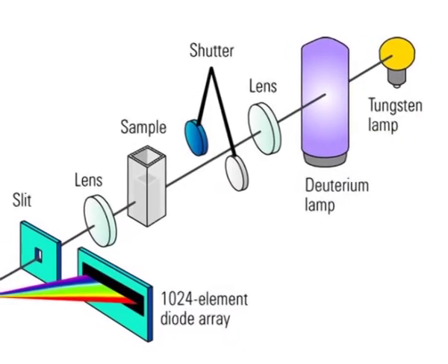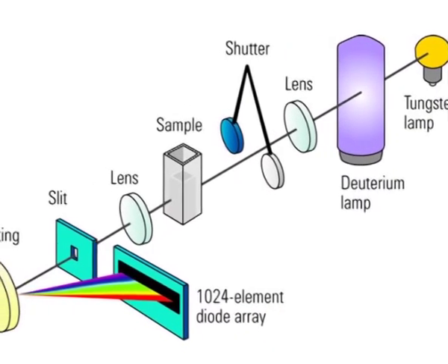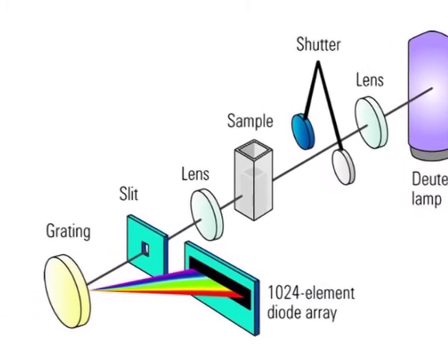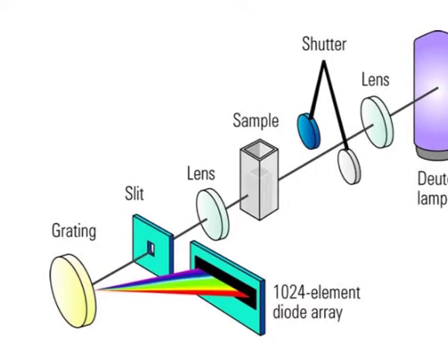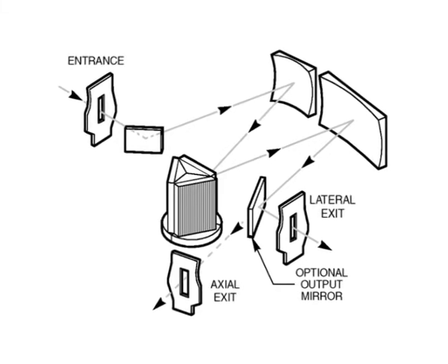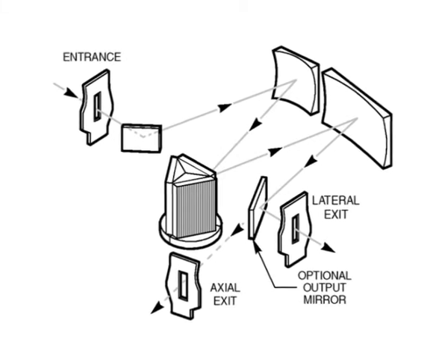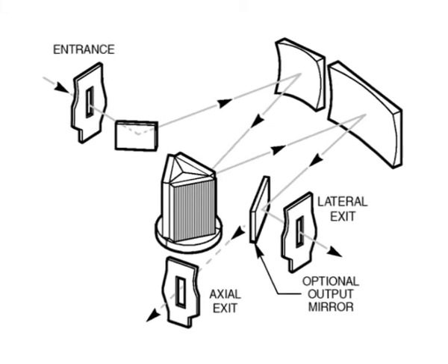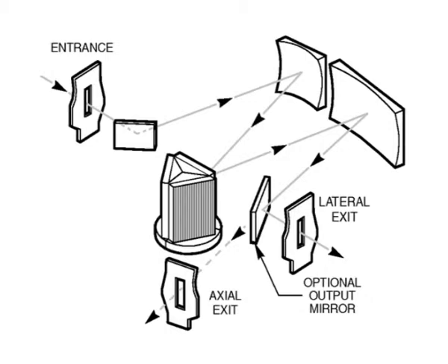The scanning monochromator moves the diffraction grating to step through each wavelength so that its intensity may be measured as a function of wavelength. Fixed monochromators are used with CCDs and photodiode arrays. As both of these devices consist of many detectors grouped into one or two dimensional arrays, they are able to collect light of different wavelengths on different pixels or groups of pixels simultaneously.